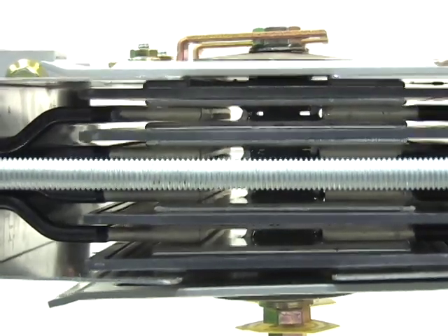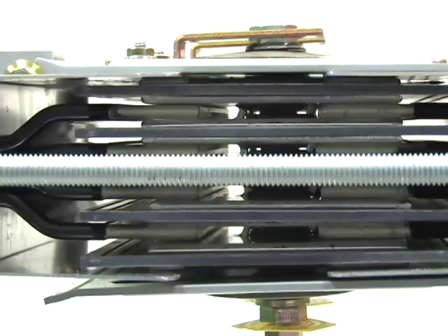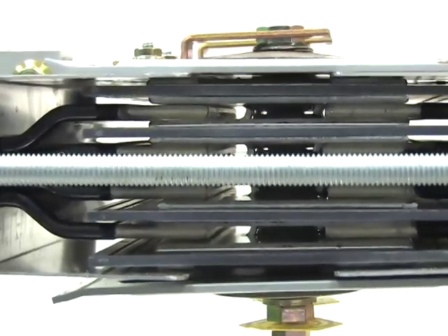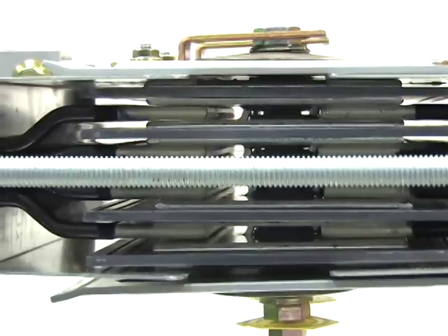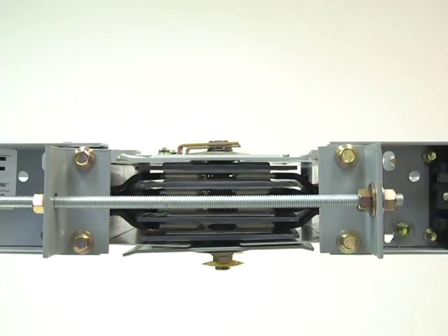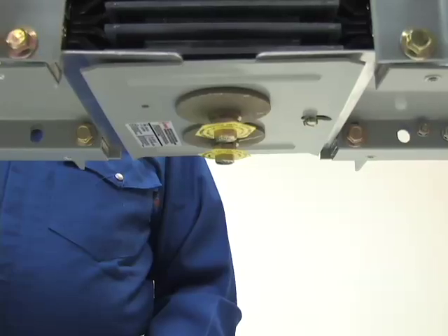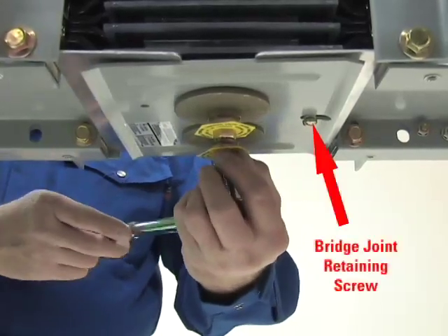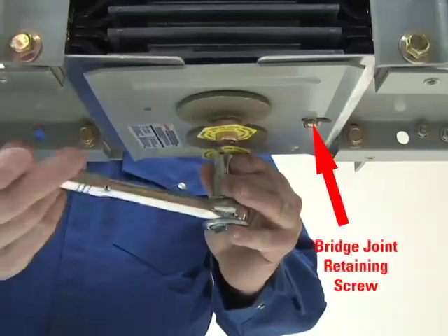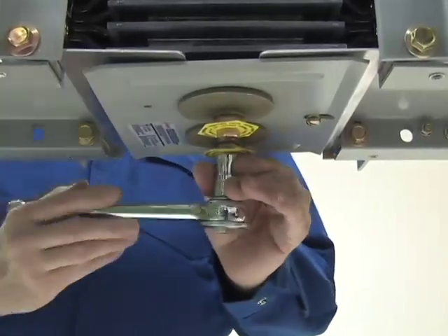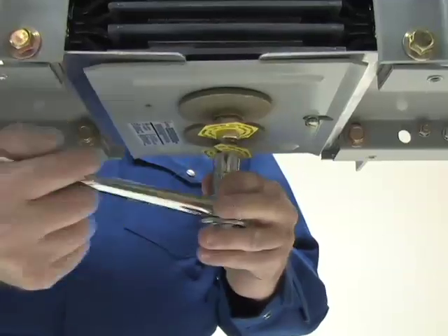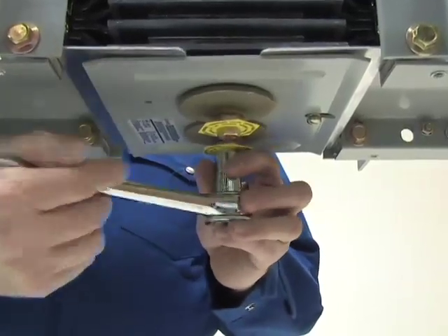When adjustment of the joint is required, remove the joint cover bolts if present. The joint puller assembly may be used to pull the busway closer together or push it apart. When the two sections have been properly joined together, the joint bolt must be tightened. This joint bolt is a special torque indicating bolt with 2 bolt heads to ensure that the proper installation torque is achieved.